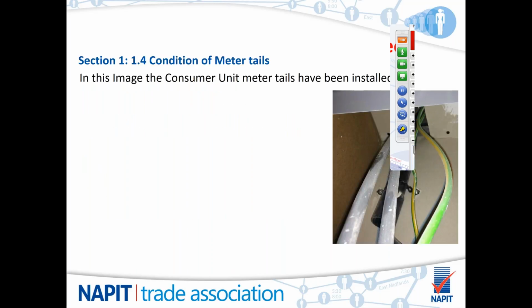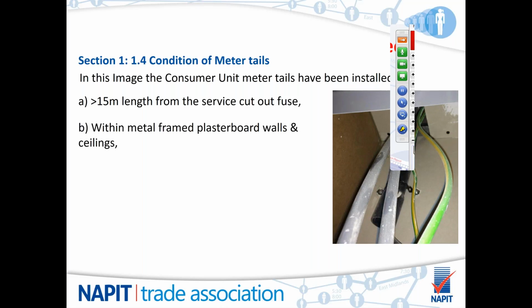Let's have a look at something here. Here's a picture of an installation that one of our members found. In this image, in this consumer unit, meter tails have been installed. We've got some tails which are over 15 meters in length from the service cutout, and it's also within metal framed plasterboard walls and ceiling.